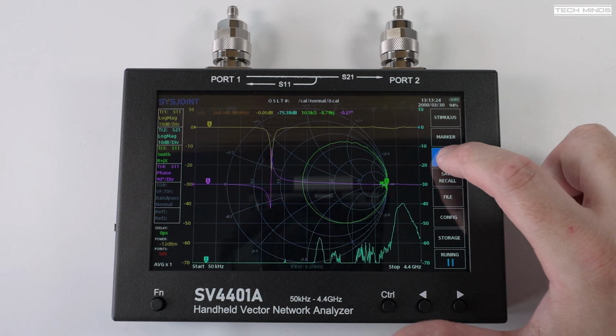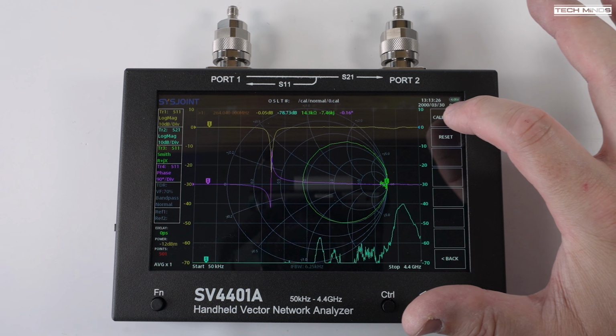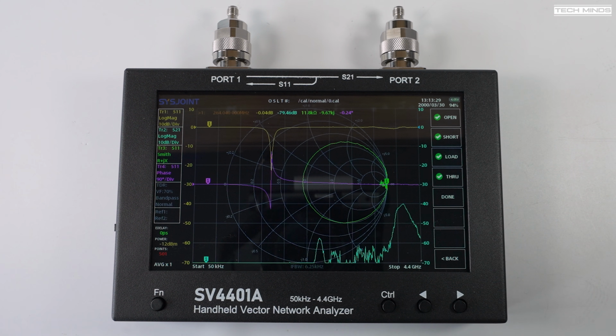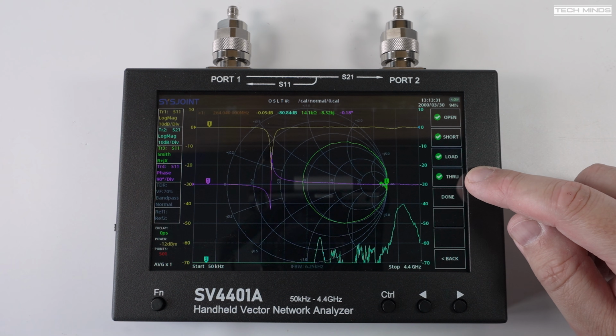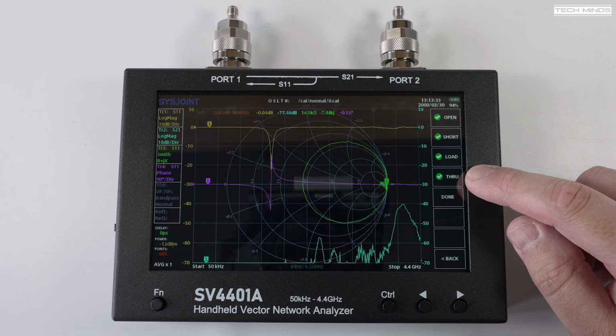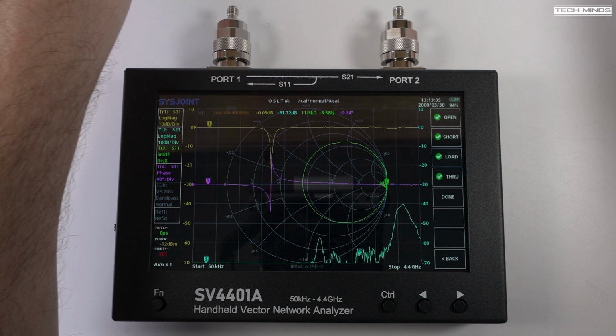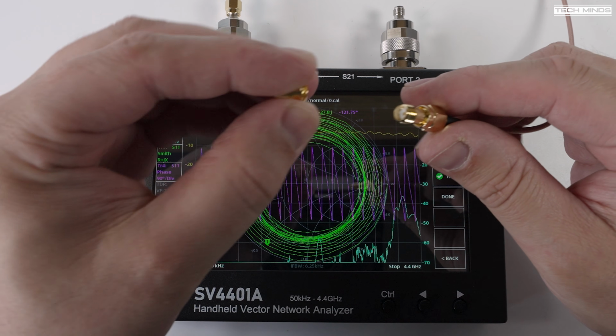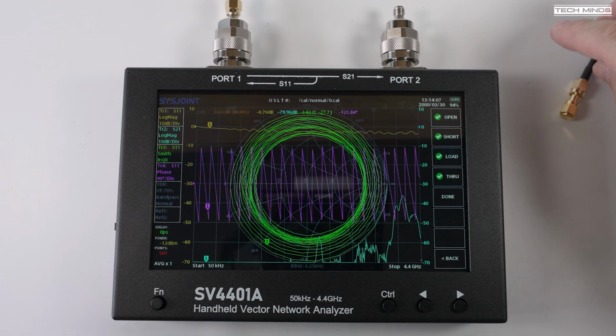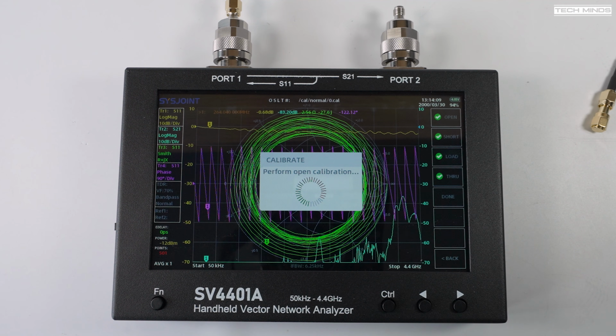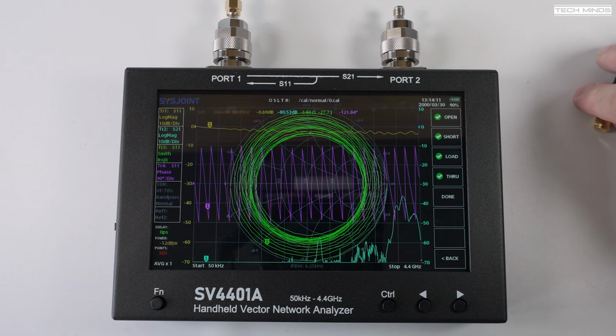Down the right side of the screen there are a few options, one of which is Cal. I'll just press this and then you have the option to go through the different calibrations. So first I'll calibrate using the open connector. It's the one without the center pin found in our accessory bag. As soon as you press open, the calibration begins, and it's rather quick, which is quite nice.